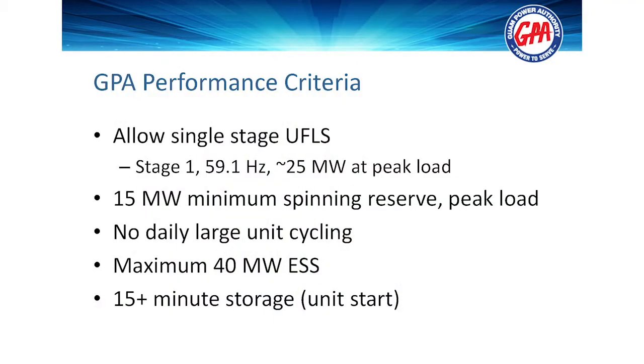This is the performance criteria. This is the biggest driving factor in energy storage for an islanded power system. What kind of reliability are you going to live with? This is the single biggest determination of what your battery storage is and what your battery storage costs are going to be. At GPA, we actually looked at several things, but they decided on a criteria that they will allow one stage of under-frequency load shedding for a single contingency.